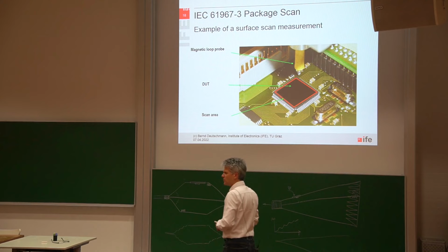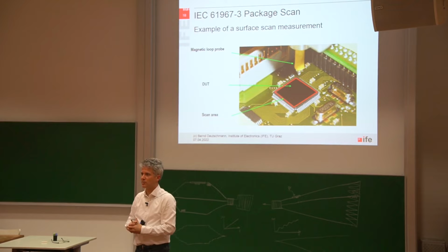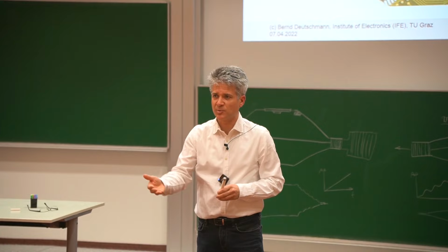So it took quite a long time because at every X, Y, Z position, we have to measure the whole frequency range, the whole electromagnetic emission, and the standard recommends to measure at each frequency position with your EMI receiver at least 3 times the operation cycle of your IC.